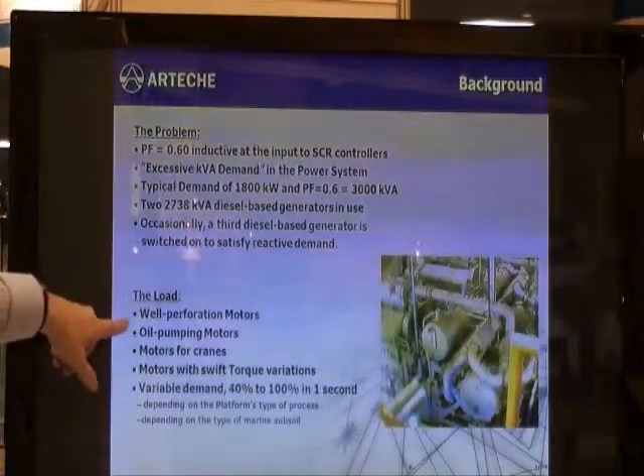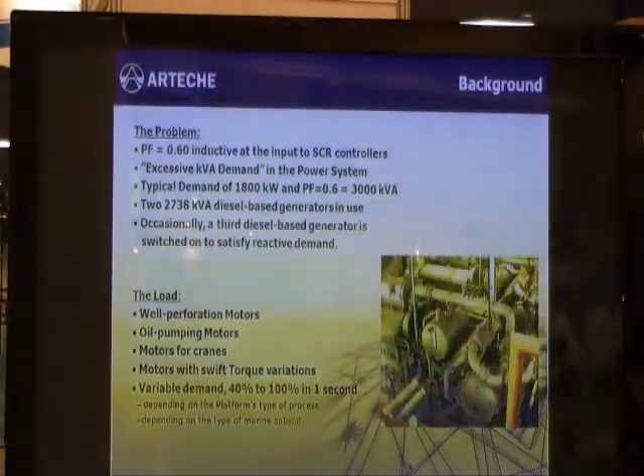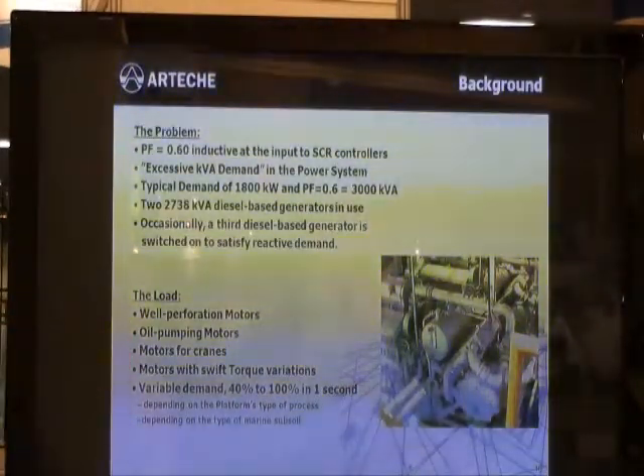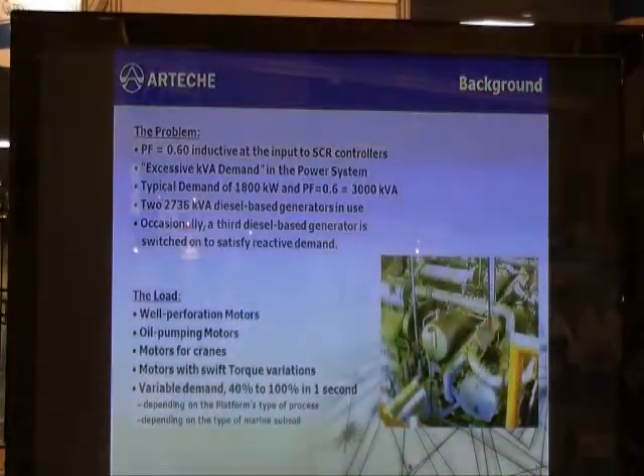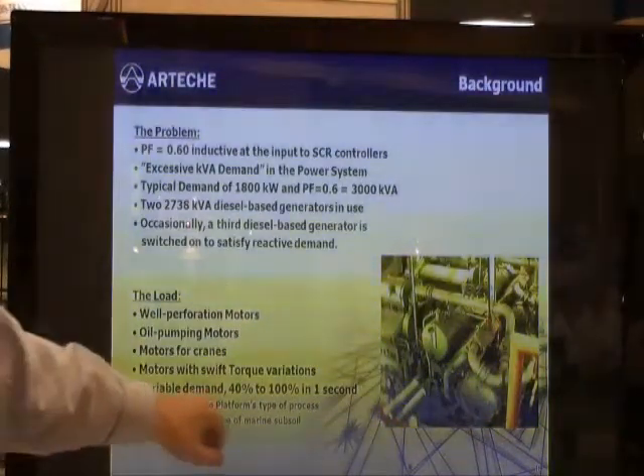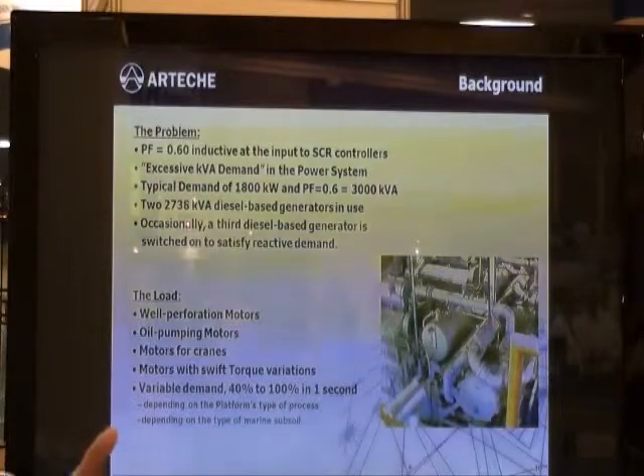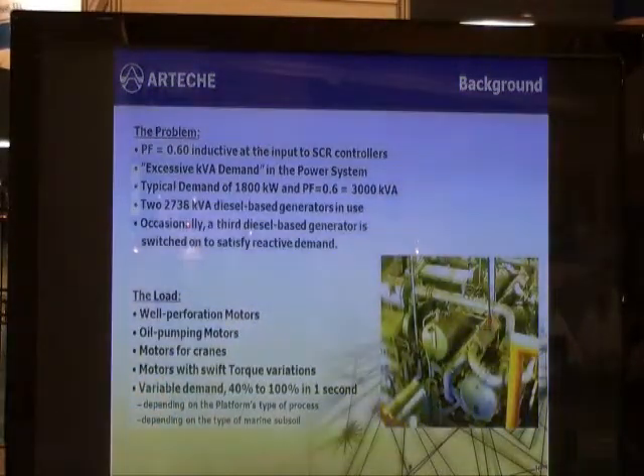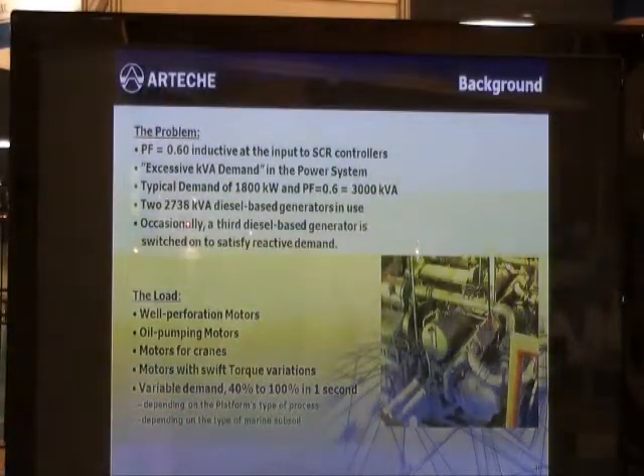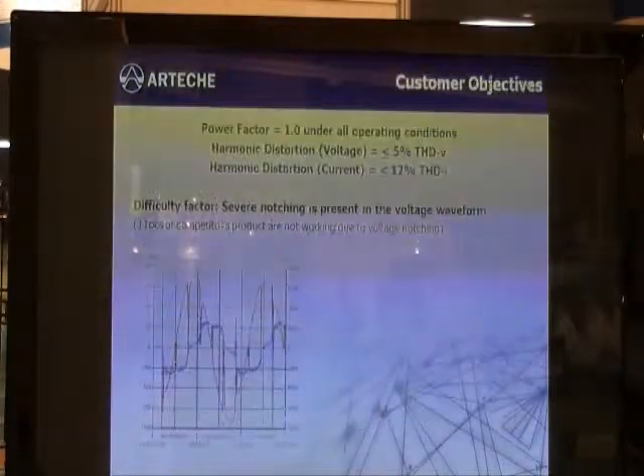The loads in this case are well perforation motors, oil pumping motors, and motors for cranes on the platform. And the demand varied from about 40% to 100% load in as little as 1 second. So it was a dynamic operation that needed to be compensated.